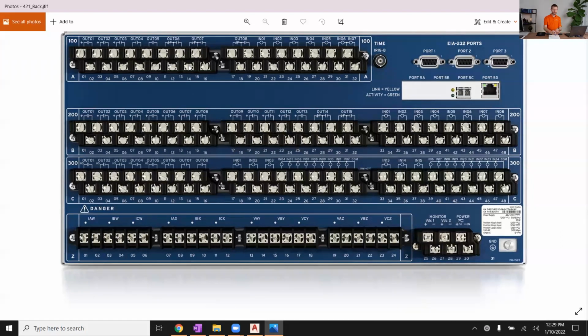I want to point out a few things to you on the back of this particular relay. This is just one manufacturer and model, but a lot of these concepts are going to be relevant regardless of what relay make and model you're using. So first, we've got a number of inputs and output contacts. I'm not going to delve into those right now. I'm going to save that for when we get into more of the DC schematics discussion. But we've got a 100, 200, and 300 board for inputs and outputs. Quite a few I/O, is how we shorten that a lot of times.